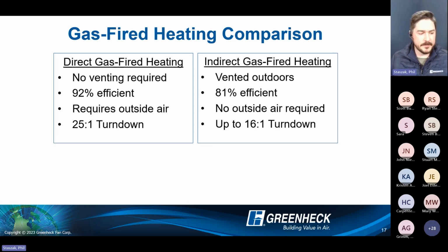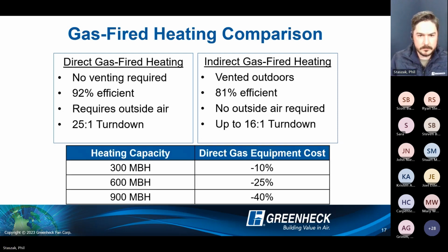Another advantage for direct gas fired heat is the highest turn down in the industry, baked into the technology: 25-to-1 turn down. Indirect gas fired heat can go up to 16-to-1 turn down, but typically we see 4-to-1 as standard as far as pricing. So that's 4-to-1 typically with indirect versus 25-to-1 with direct gas fired. We'll talk about what that turn down capacity means. It's really tight temperature control is what it boils down to, but I've got a couple of slides that discuss what that looks like further, especially with indirect gas fired.